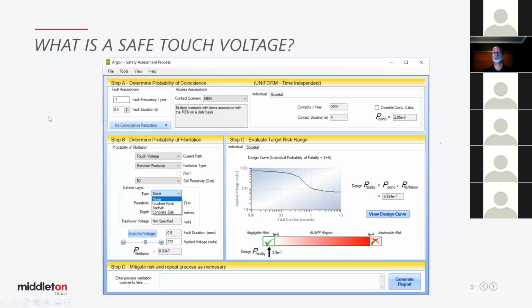We're using standard AS 2067, for instance, being a probabilistic standard. There's a nice bit of software called Argon that we can put some inputs into, and it'll tell us what the allowable voltage is. So here's our allowable voltage down here.